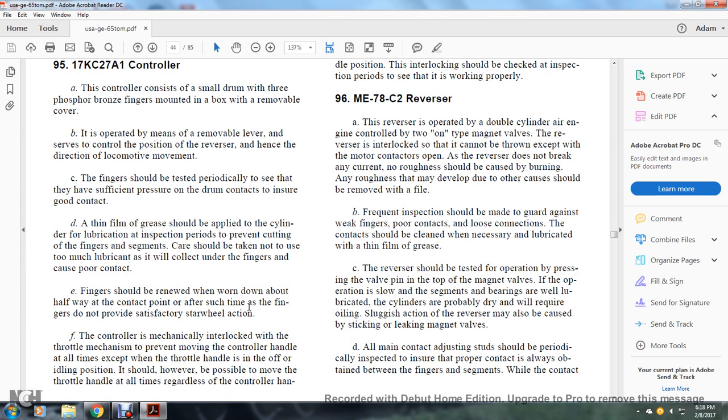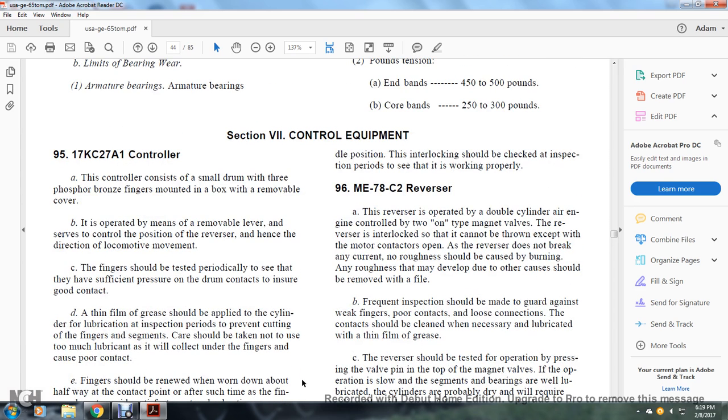A thin film of grease should be applied to the cylinder for lubrication and inspection periods to prevent cutting of the fingers and segments. Care should be taken not to use too much lubrication as it will collect under the fingers and cause poor contact. The fingers should be renewed when worn down about halfway to the contact point, after which time the fingers do not provide a satisfactory star wheel action. The controller mechanically interlocks with the throttle mechanism, preventing movement of the controller handle except when the throttle handle is in the idle position. The interlocking should be checked at each inspection period to see if working properly.